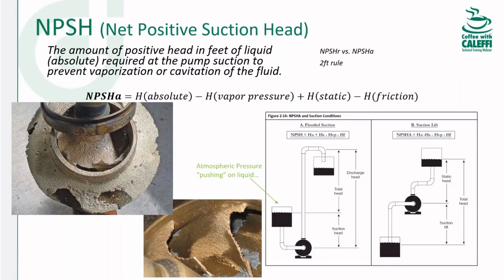And also on the Grundfos, if somebody said they were doing a suction lift job, we would put check valves on the inlet side and then have a very small manifold bypass. So when there's no flow, the high pressure bleeds back to the suction side, and that helps seat the foot valve that would be down here. That way you maintain your prime. So just some ideas.